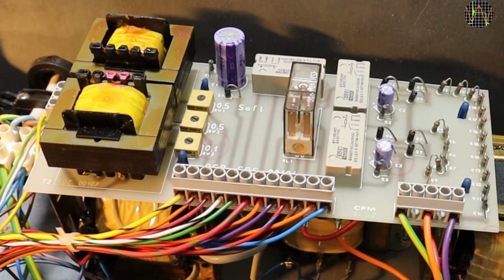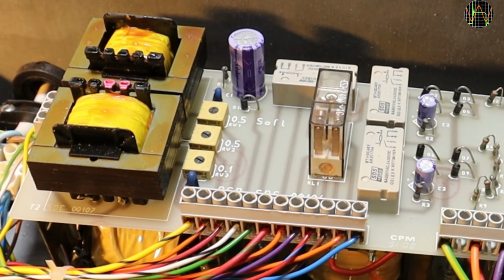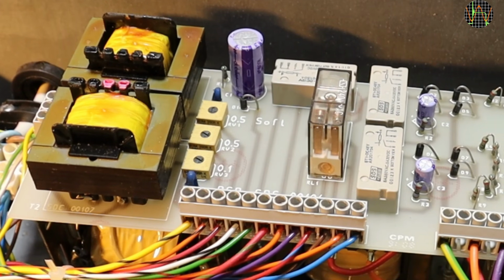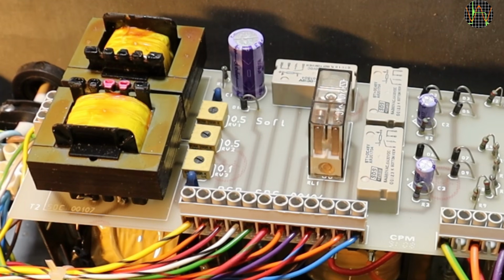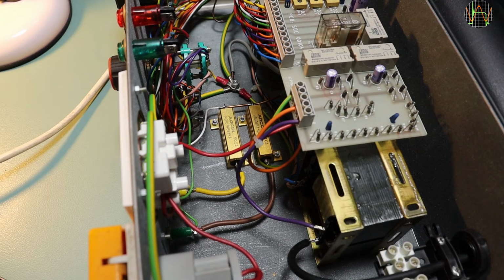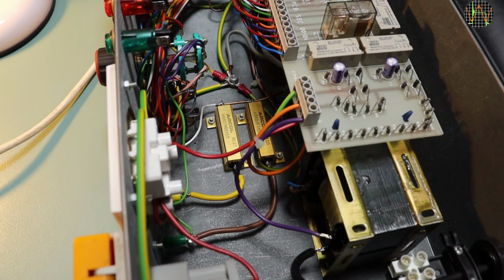There are 3 trim pots for calibrating the class 1 earth resistance measurements on the PCB, but there is nothing similar for the high voltage insulation measurements. It comes directly from transformers out of the mains voltage. This means the value will fluctuate, which could explain why the class 2 measurements were lower than expected. There are 2 50-watt power resistors mounted on the bottom.